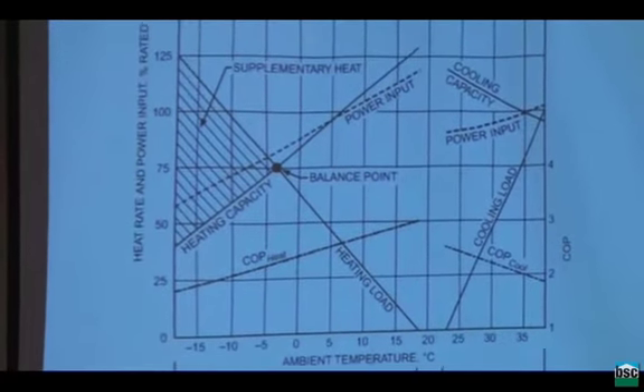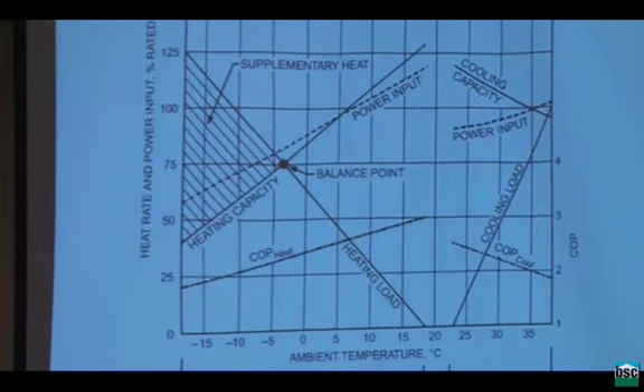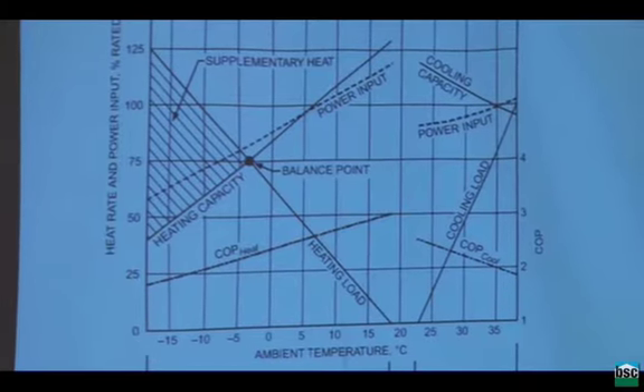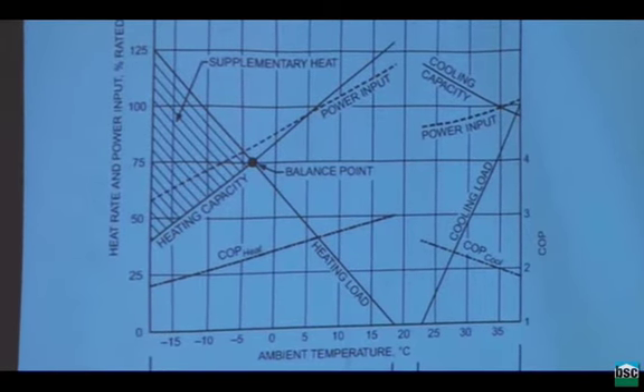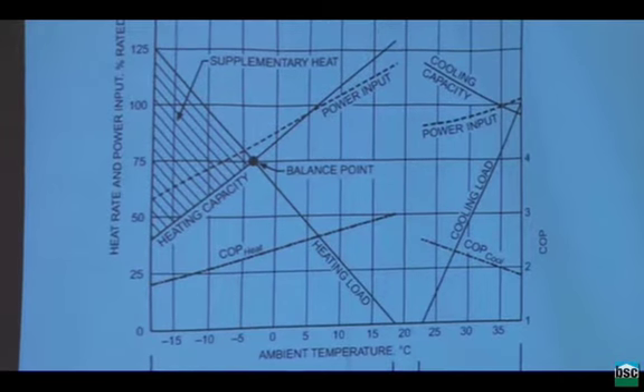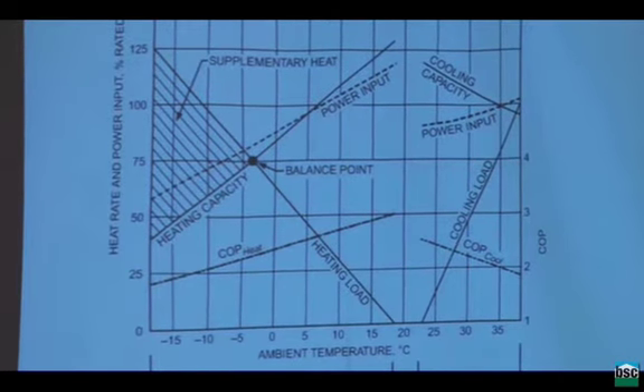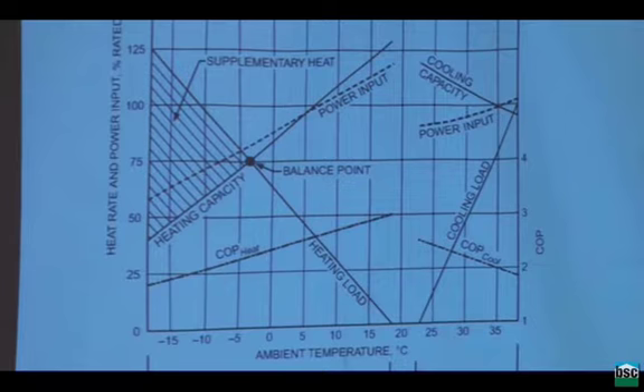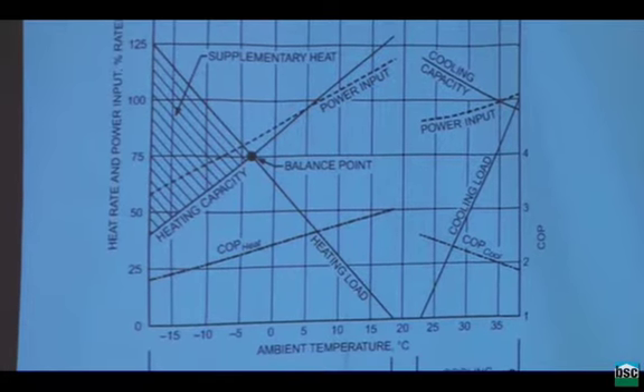Your capacity at 0 degrees Fahrenheit on today's heat pump will be about 1/3 of what it is at the rating condition. So if you need 12,000 BTUs an hour at 0 degrees Fahrenheit, a rule of thumb is buy a 3-ton heat pump, 36,000 BTUs an hour. If you need 24,000 BTUs an hour, then you need to buy a 6-ton heat pump, because the capacity at around 0 is 1/3 of what it is at the rating temperature. That's a big deal, right?